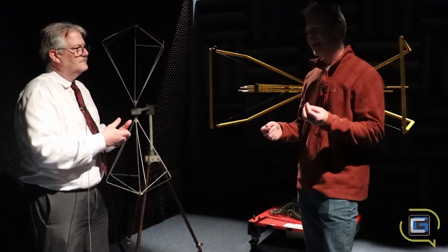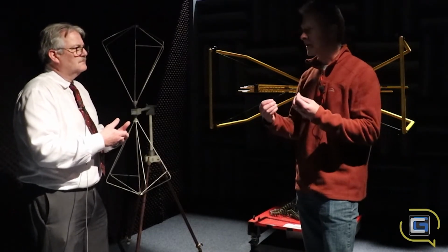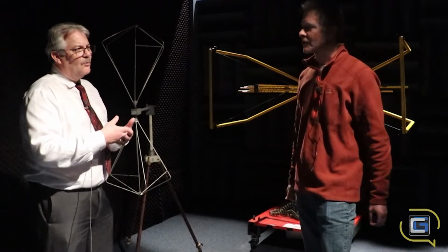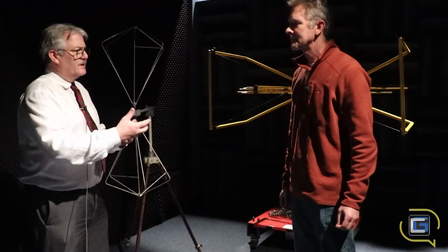The reason is that we use a lot of COTS, commercial off-the-shelf power supplies, which we don't have control of how their emissions are being generated, and so that's where we have the problem. Okay. Well, once you find that situation, what do you do to knock down that problem in terms of conducted emissions?